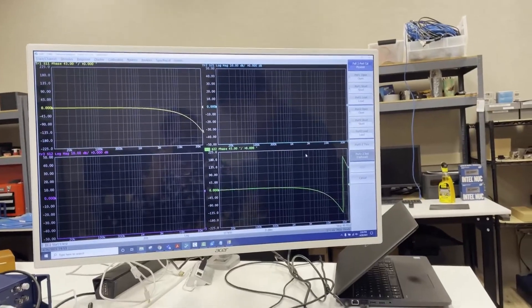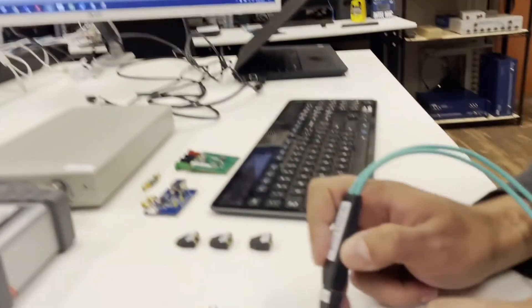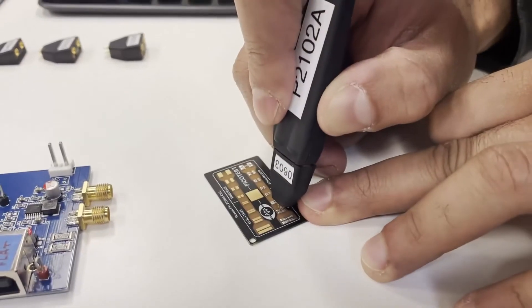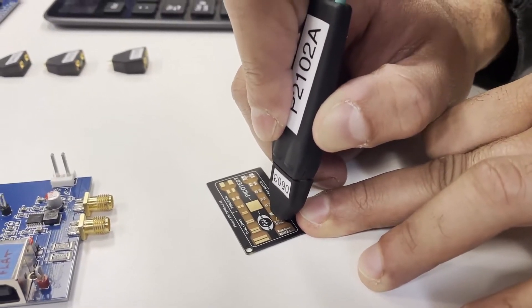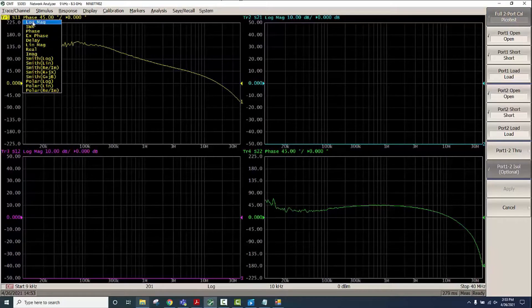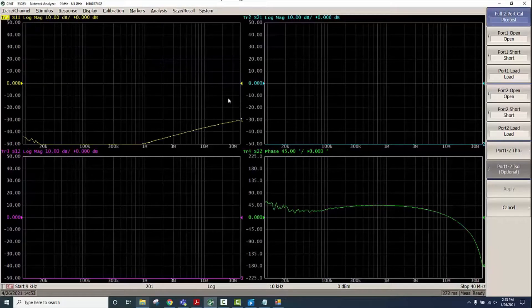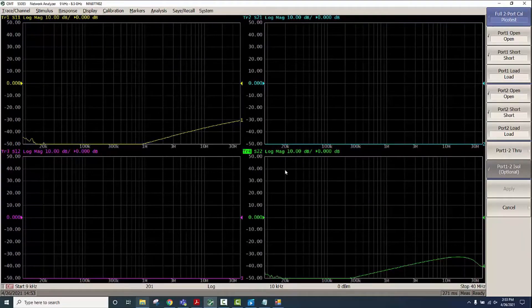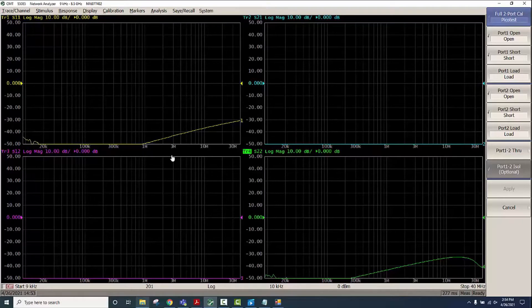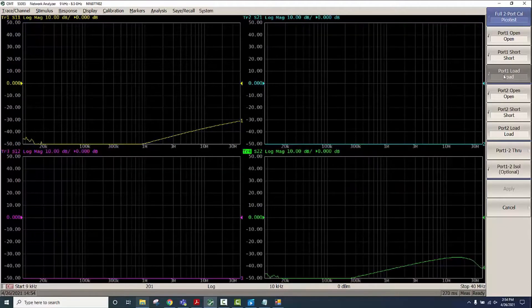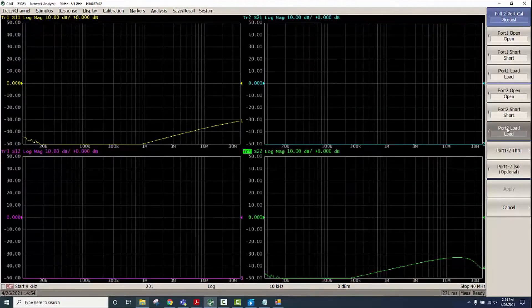Next we will do the Load. For that we will look at the S11 and S22 log mag response. You can see pretty decent return loss there on S11 and S22, so we'll click on Load on Port 1 followed by Load on Port 2.